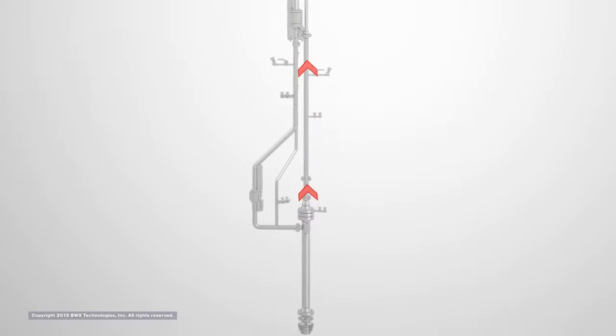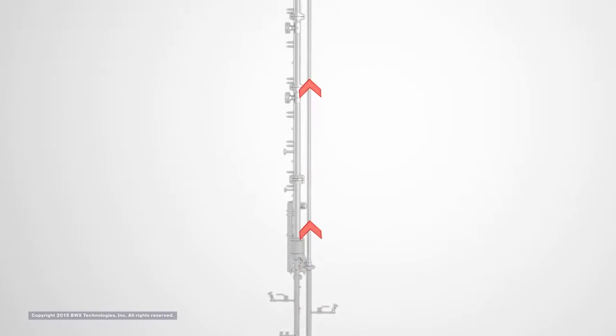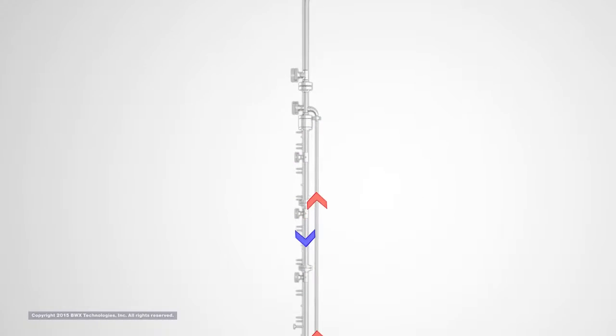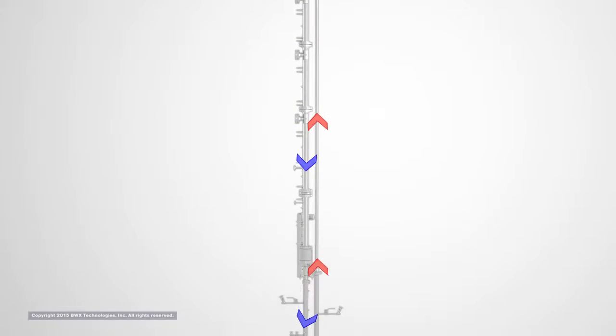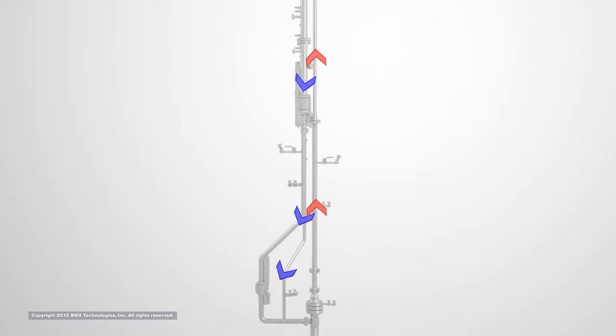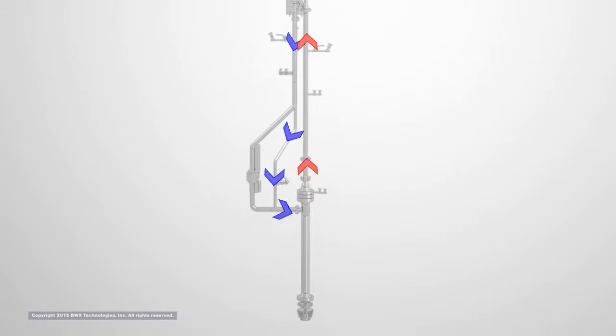The principal prerequisite toward that objective is the requirement for full pressure and temperature. As a design reliant on inherent safety from passively occurring phenomena such as natural circulation, full height scaling was considered to be the next dominant scaling priority. Maintaining full height and the ratio of power to volume, realistic loop flow transit time is preserved.